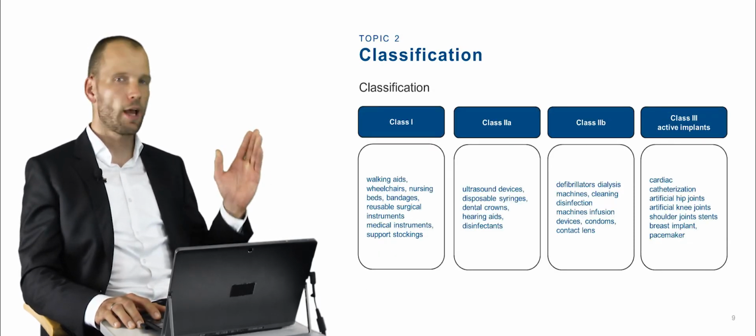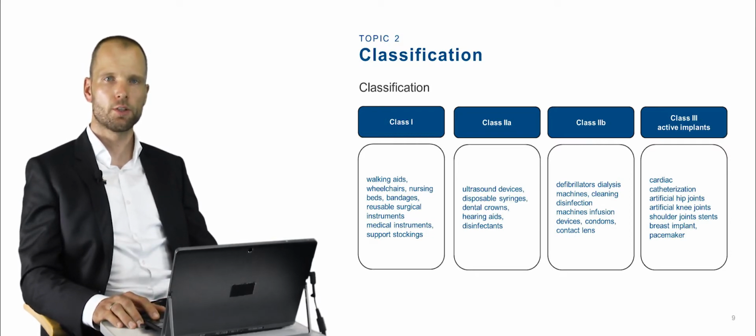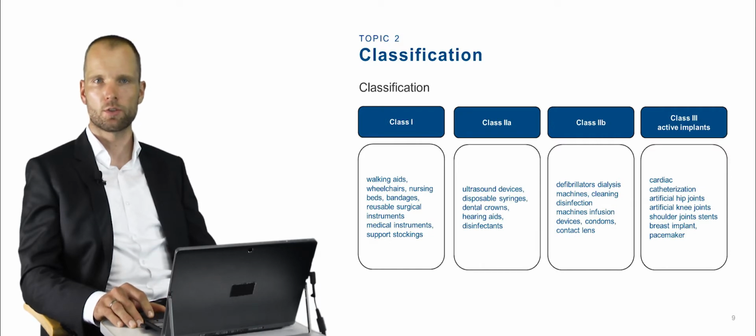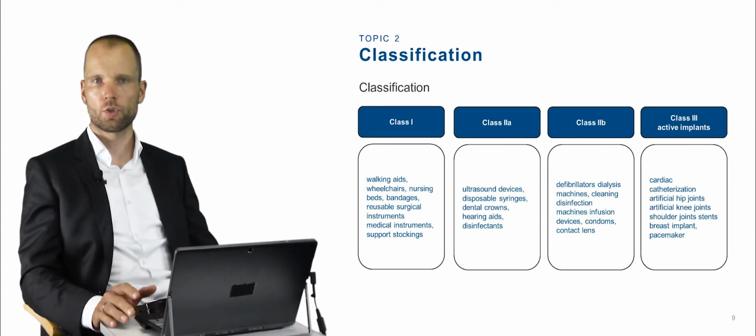On the following slide, I have some examples of which medical device belongs to which class. Class 1: medical instruments or support stockings. In Class 2A are hearing aids and disinfectant. In Class 2B are condoms or contact lenses. And in Class 3, breast implants and pacemakers.